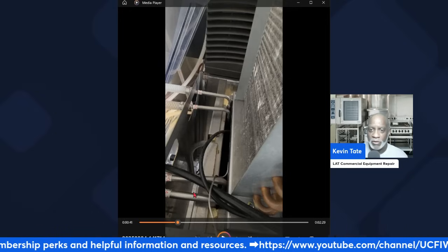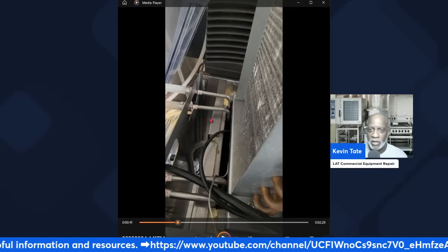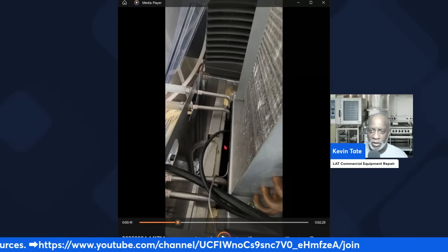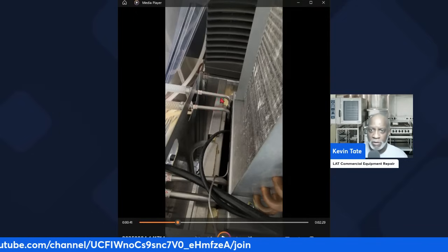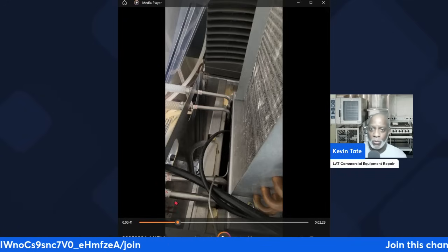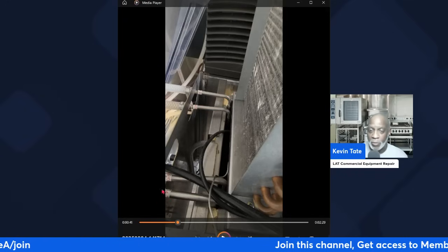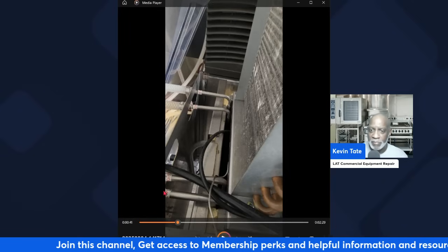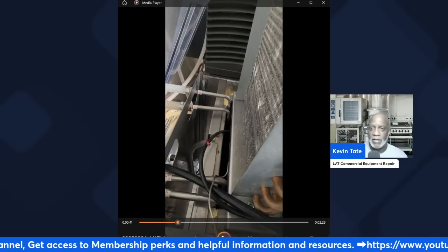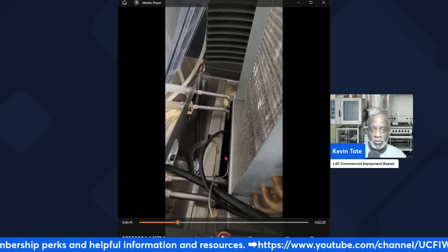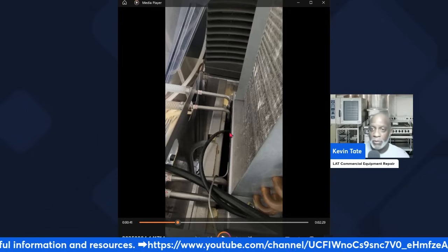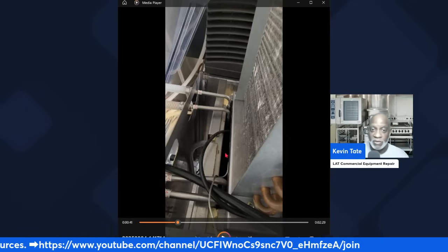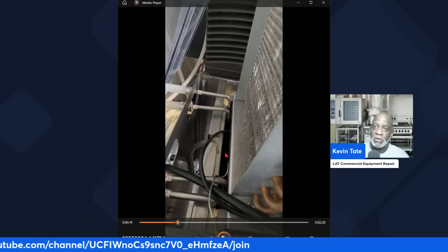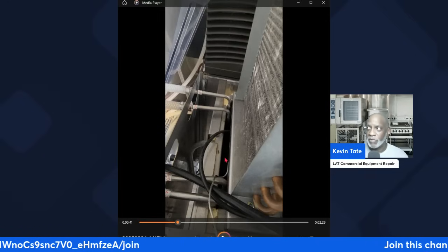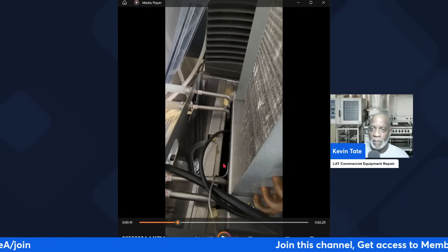Right here there are four stainless steel lines going down into the water bath. You can't see it very well right now, but the inlet line is on this bottom section of the screen, and that's where the water goes in, and the tank is supposed to be full of water. But what I found was that the tank was empty - it was never filled. That's a mistake that some technicians do tend to make when installing these.